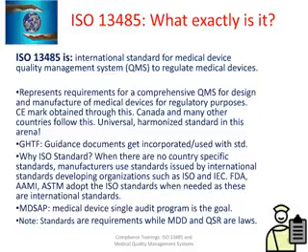Now moving on. There are guidance documents like GHTF, Global Harmonization Task Force. They are all used in addition to the standard, and they help guide us on what exactly the standards mean. There's always an explanation for the standard. I have a copy of ISO 13485 right in front of me, where there are different sections like the scope. There are also the definitions, and then there's each element and how it is interpreted. There are also questions that you ask based on the elements of ISO 13485.